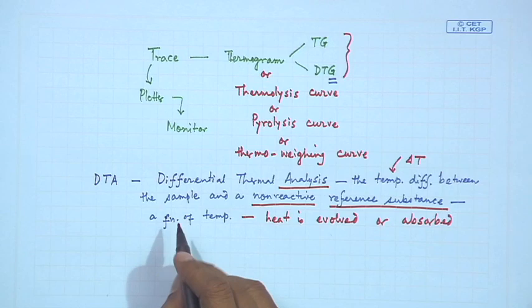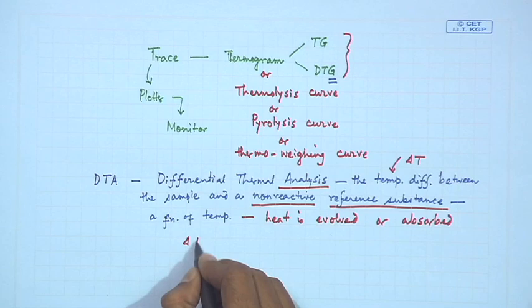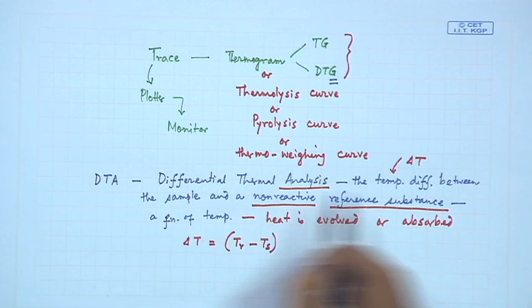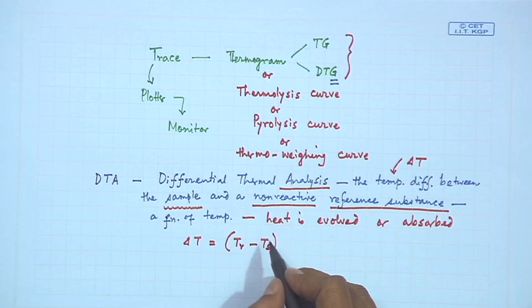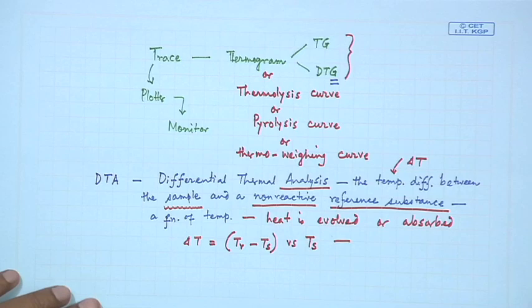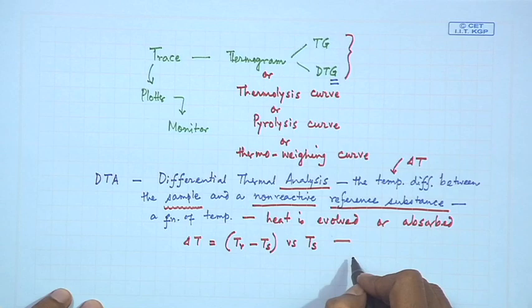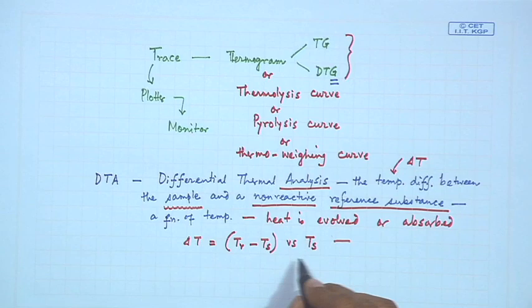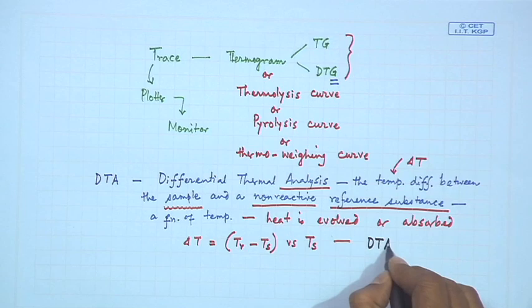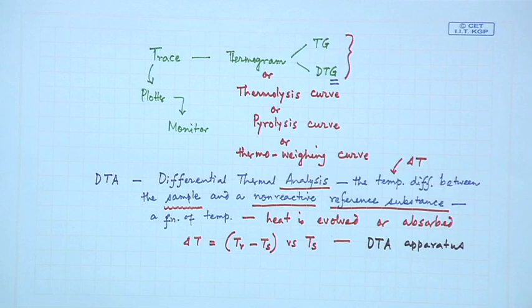Delta T is the temperature of the reference minus the temperature of the sample, plotted versus the temperature of the sample. The reference material is inert and non-reactive, so it does not undergo heat evolution or absorption. A dedicated DTA apparatus is used — not a simple thermobalance — and we obtain a DTA curve or DTA plot from the instrument.